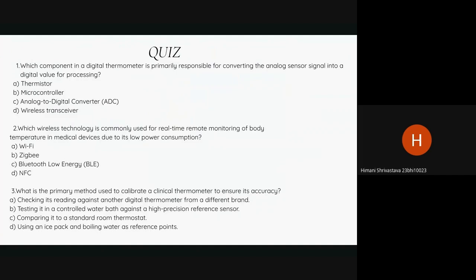The third question is, what is the primary method used to calibrate a clinical thermometer to ensure its accuracy? For this, the correct answer is testing it in a controlled water bath against a high precision reference sensor. So, this method provides a stable and uniform temperature environment, allowing for a precise comparison of the thermometer readings against the known, highly accurate standard. This is a far more reliable method than using less precise or variable reference points like ice packs or other commercial thermometers.